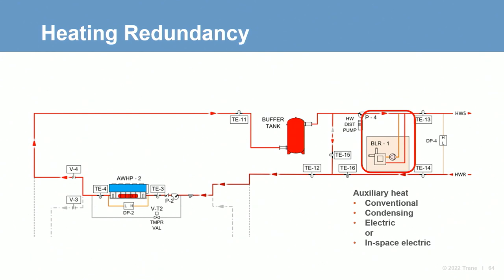As shown here, when auxiliary heat is applied in the hydronic system, it is best connected into the heating distribution loop supply line. This position has the advantages of allowing the auxiliary heat to supplement the heat pump capacity when required or provide standalone heating when the heat pump production plant is shut down. The auxiliary heat source can take practically any form, from low-cost conventional natural gas boilers to electric heat.